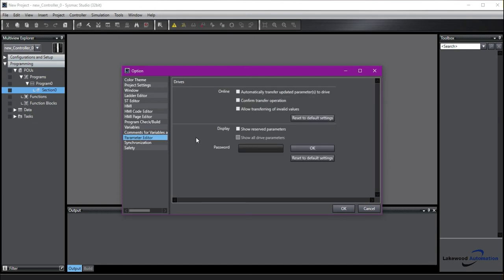Parameter editor. This is for drives, so motion. I would leave all these unchecked. Normally, once you have a drive set up and the parameters are set up, you do not want them to be updated. If you change something in the program, you're just looking at different parameters. This will automatically change them if you have it checked. So I would recommend leaving them unchecked.